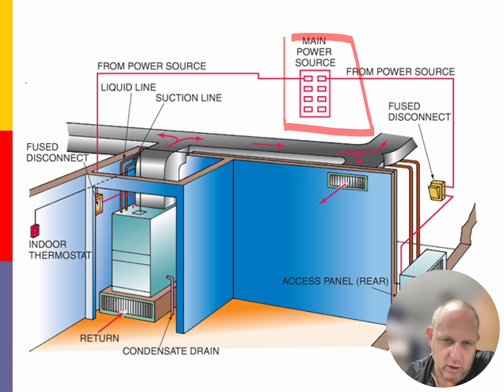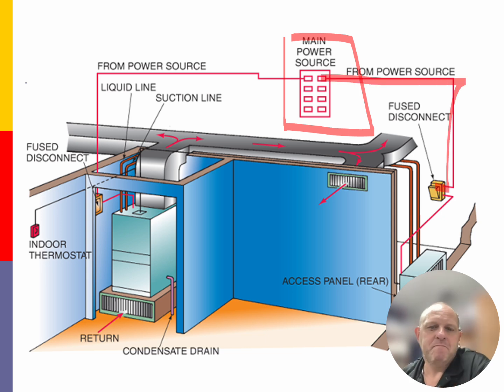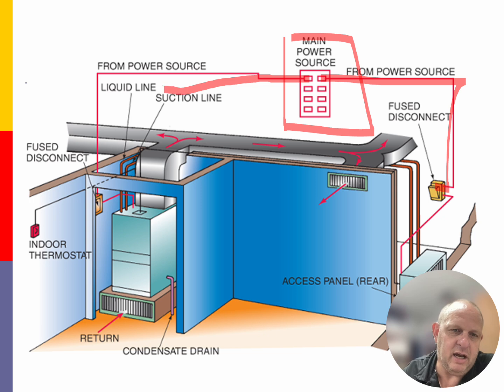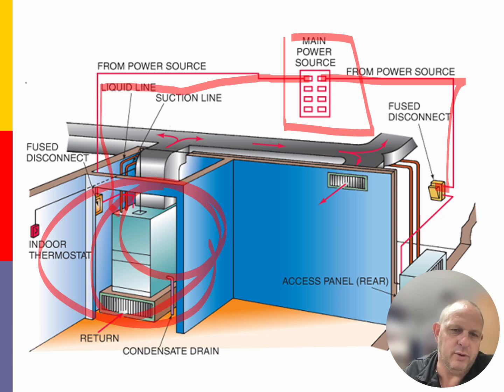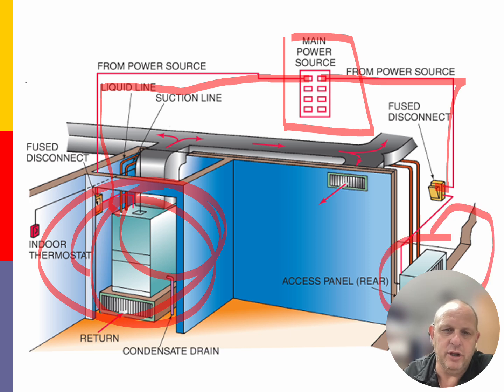And remember, the disconnect always needs to be within reach of the outdoor unit, or within 5 feet of that outdoor unit, so we can turn it off quickly or do something that we need to do as we are servicing that unit. Power supply will then be run from the breaker box into the indoor unit, which is sitting over in this location here. Here's our outdoor unit, here's our indoor unit, and then here's our main breaker panel for the wires that we are going to be running on that particular unit itself.